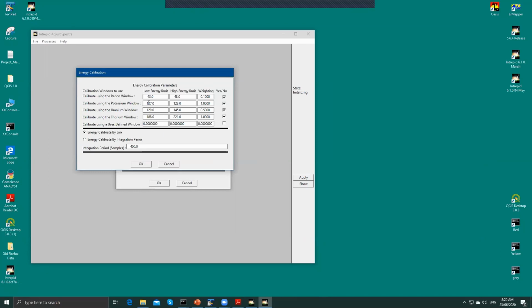Okay, cool. The first thing it does is look for a peak in the specified bandwidth. So for potassium, from channel 107 to channel 123, and then it wants to move it to the theoretical position, which is not these channels. So you have to pick these channels correctly, because if you identify them wrongly, they can't detect the peak. So that's where we come to the extras.